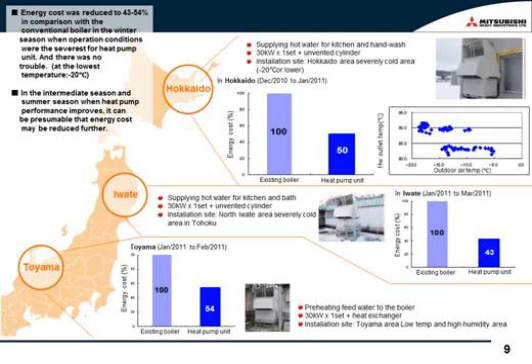We conducted winter field tests in 3 sites, that is, Hokkaido, Toyama, and already mentioned Iwate. The meteorological condition in winter is very severe in each place. The running cost of every site dropped by as much as 50% during the winter. And also, please note that heating efficiency in winter is the lowest of the year, so it follows the annual running cost will be lowered still more. Therefore, we can say Q-ton certainly has a very good effect on a running cost side and an environmental side.